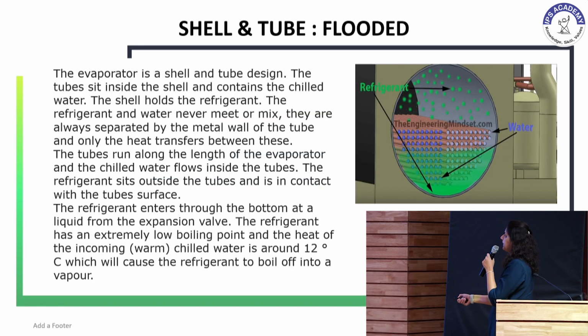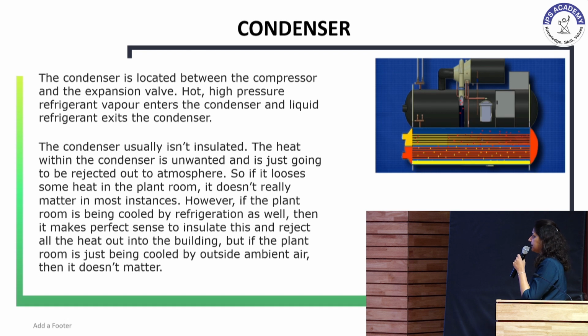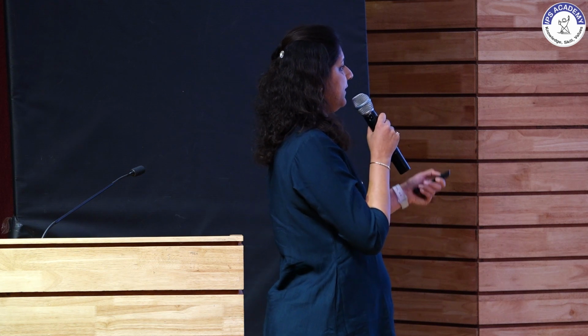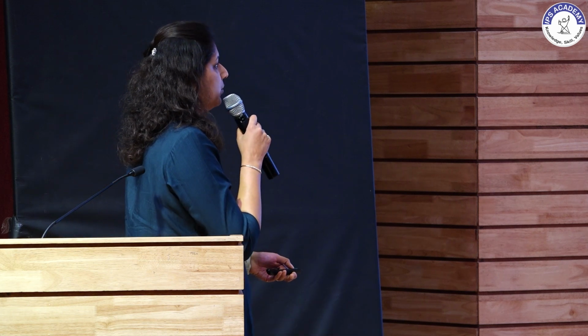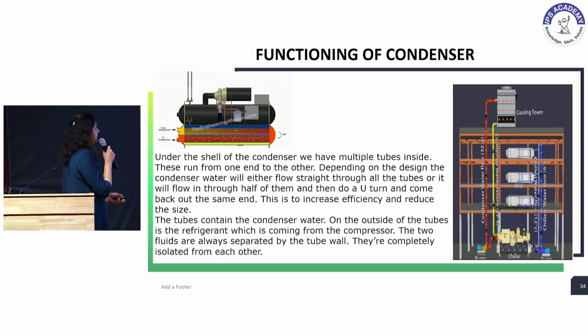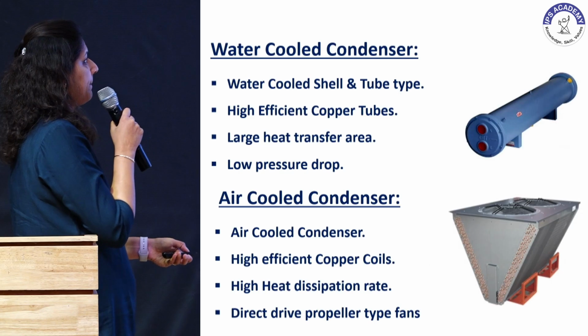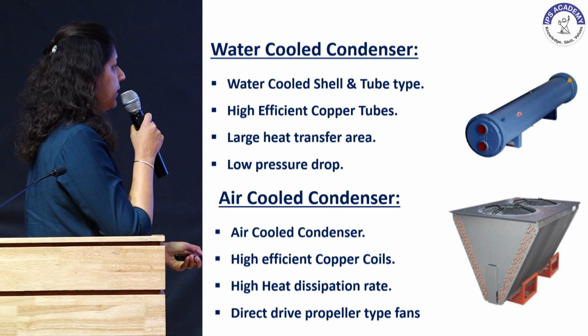So I have already described this. Then again we have condensers. The condensers are usually flooded where the refrigerant is in the shell and the water is in the tube. Again, the condensers can be a single pass or a double pass condenser. We choose it in relation to the heat exchange area which is required to design that specific refrigerant cycle. So condensers again can be, as I have described, air-cooled or water-cooled, and the water-cooled system can be either shell and tube or the air-cooled coil type condenser. So if it is a shell and tube condenser, it will be attached with the cooling tower to dissipate the heat to the environment. The first picture you see is a water-cooled condenser, and the second picture you see is an air-cooled condenser.